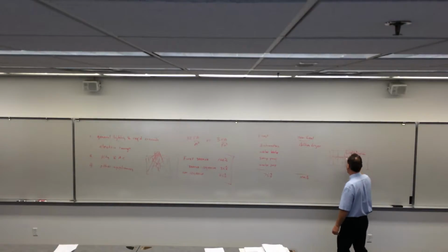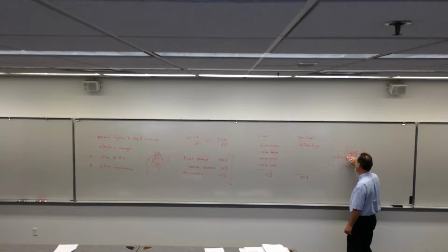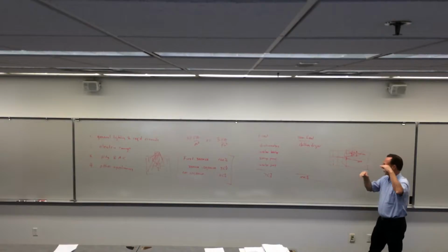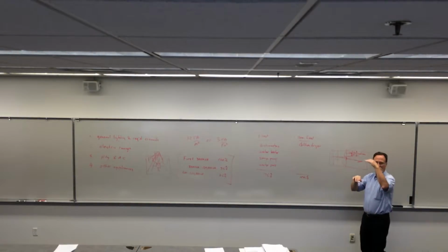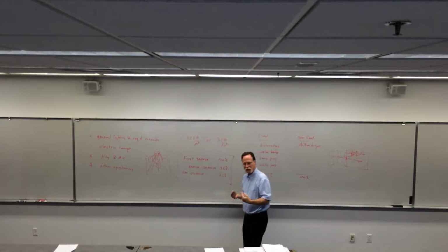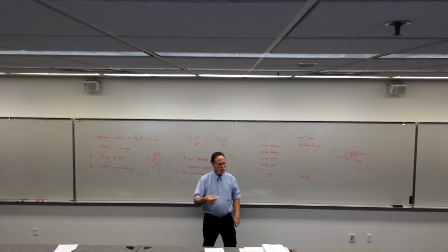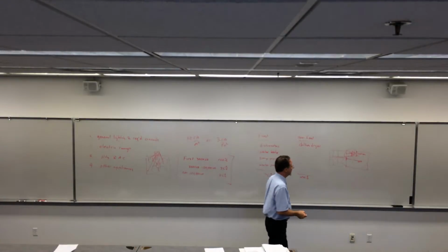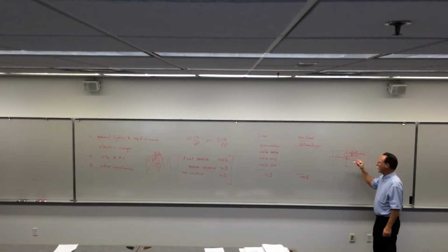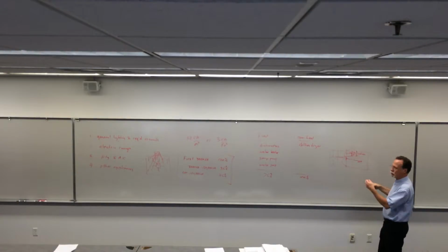I actually have a drop ceiling, so to speak. I can put sidewall diffusers here to get the air conditioning over here, and I can put my ductwork in that differential space from the 9'4" to 8 foot. I can put my ductwork right in there and have all my ductwork inside conditioned space, which is not up in the attic and being too hot. So if I design everything right, I can put my ductwork in a more convenient space for its cooling job.